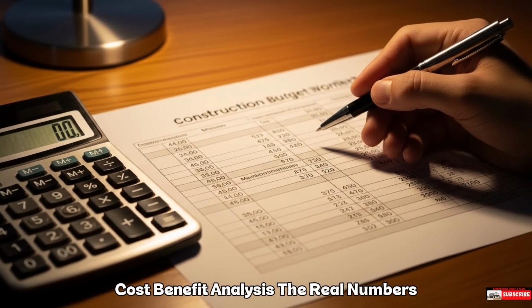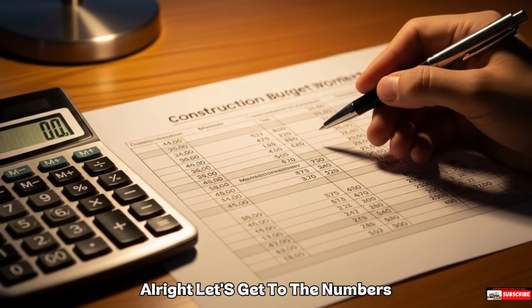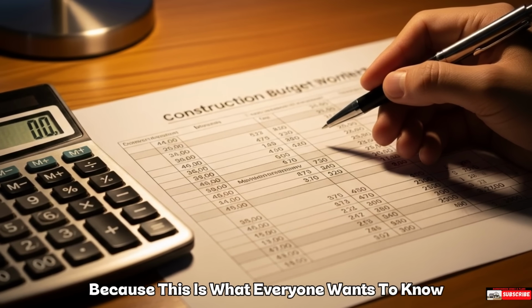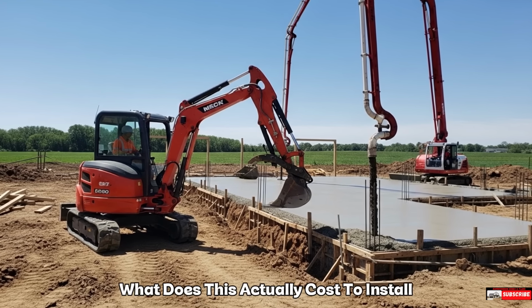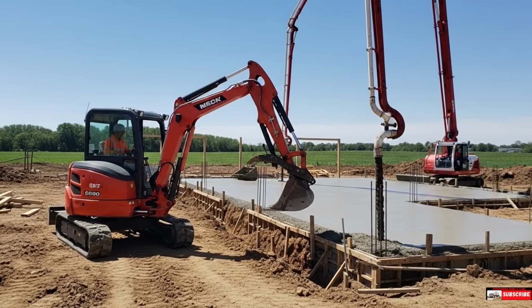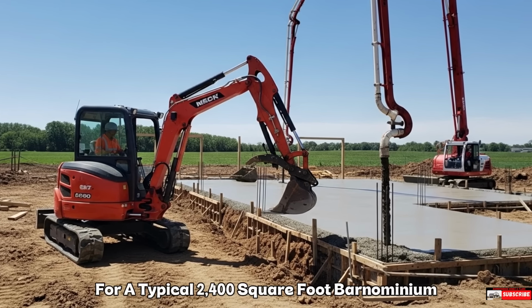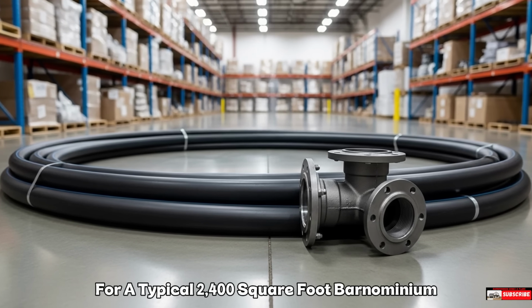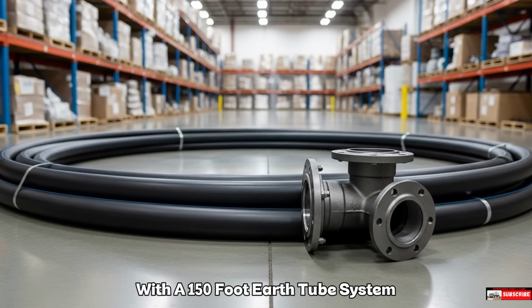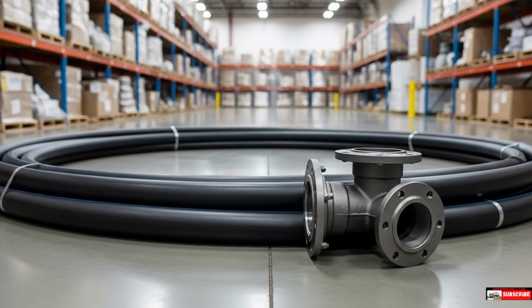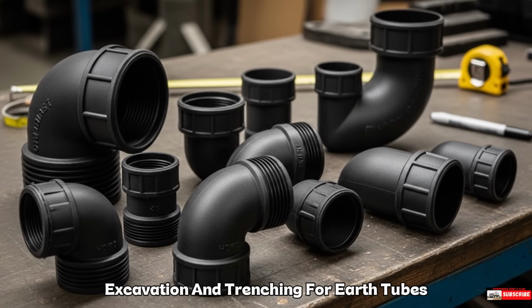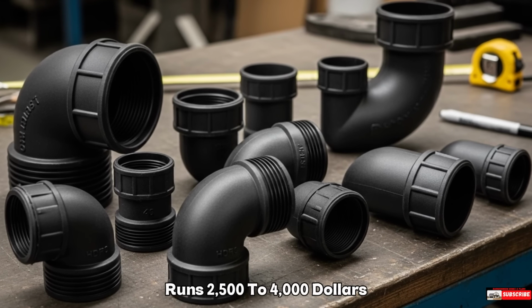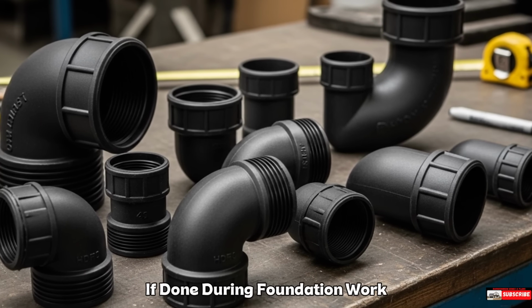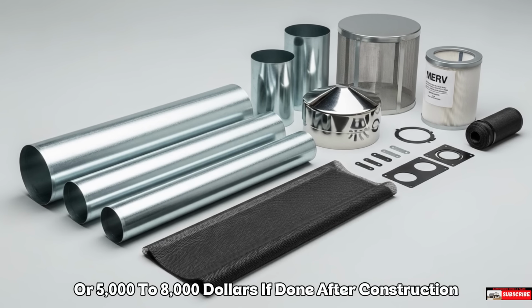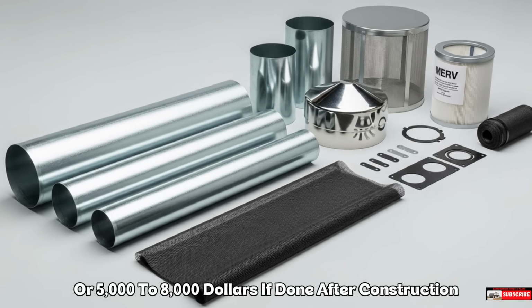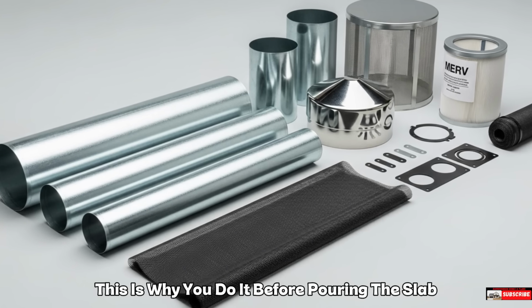Cost-benefit analysis, the real numbers. All right, let's get to the numbers because this is what everyone wants to know. What does this actually cost to install, and is it worth it? Initial investment breakdown for a typical 2,400 square foot Barndominium with a 150-foot earth tube system. Excavation and trenching for earth tubes runs $2,500 to $4,000 if done during foundation work, or $5,000 to $8,000 if done after construction. This is why you do it before pouring the slab.